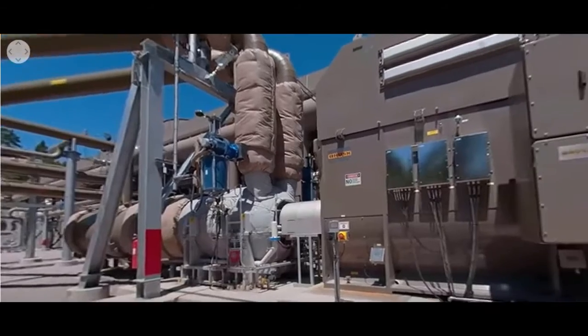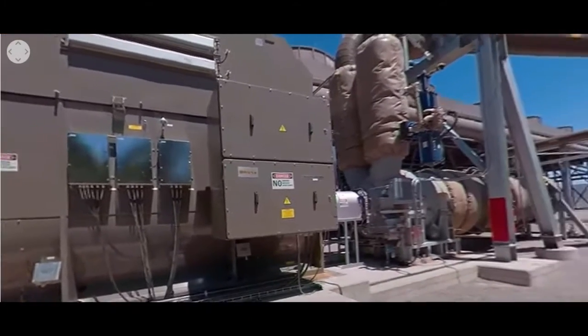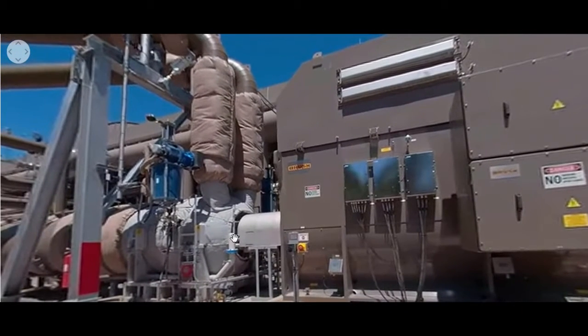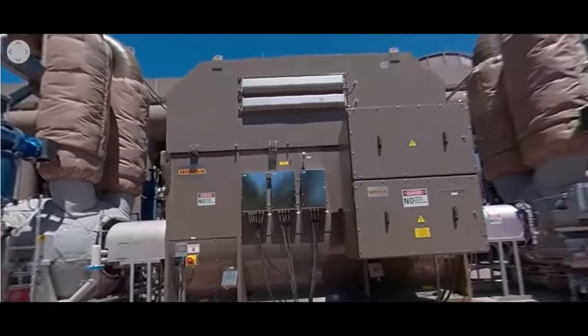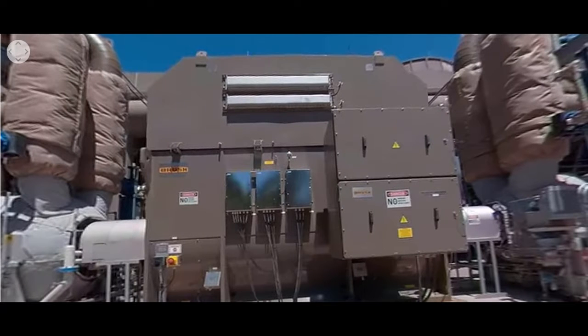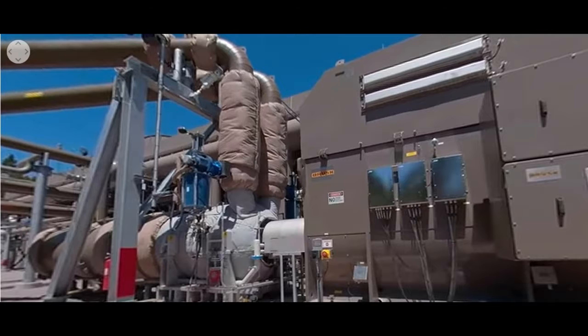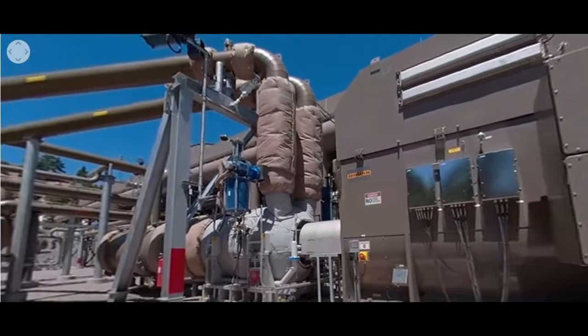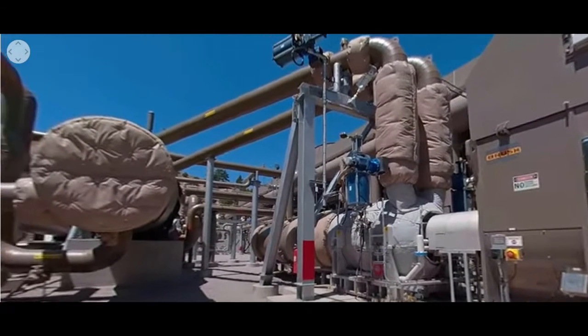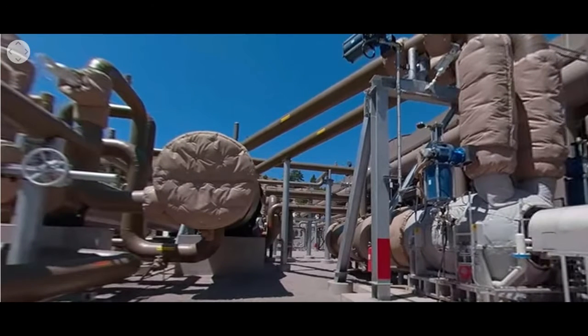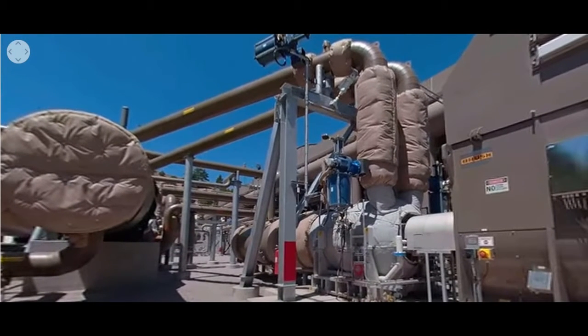Steamboat Hills is what is known as an integrated 3-level facility and has a total of 3 turbines. Our turbines are the single most important element of an Ormat geothermal power plant. The turbine, rotating by the force of pressurized vapor, rotates the generator, producing clean electricity with 0 carbon emissions, 24 hours a day. From the initial single-stage turbine designed in 1965 to our newest 5-stage turbine today, the improvements in our turbine designs have set us apart from our competitors. And with 400 million cumulative working hours, we've had plenty of time to perfect their performance.